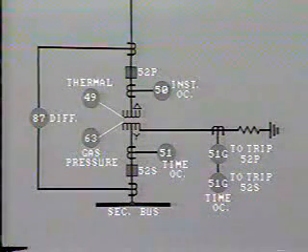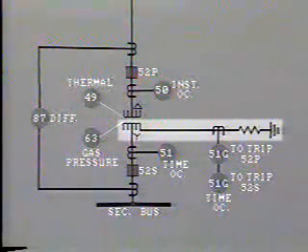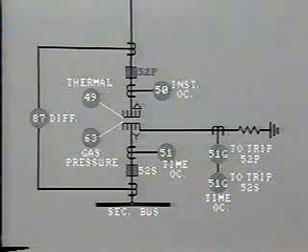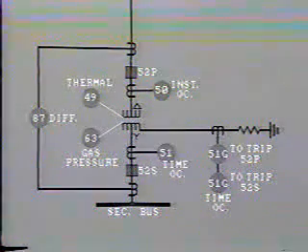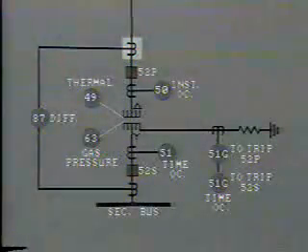What else does the diagram tell us? Well, we can see that the primary is delta connected and the secondary is Y grounded through a resistance. The circuit breakers are represented by 52P primary and 52S secondary. What do these other device numbers represent? Looking up our reference list, we find that the transformer itself is equipped with a thermal relay, 49, and a gas pressure relay, 63. This is a commonly used symbol for a CT, but please make sure you are familiar with your own company standards.